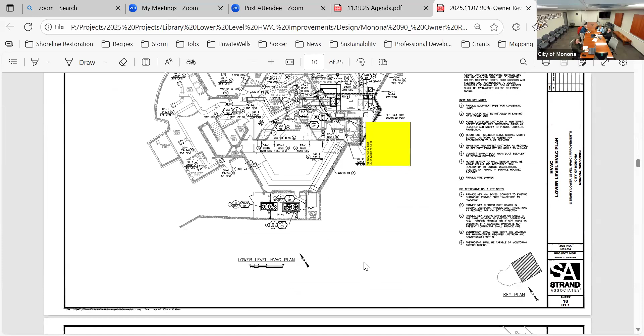We are also going to be replacing the heating coils downstairs. Basically that's downstream on the ductwork, far from the air handler. In a dedicated space, there will be this little hot water tube in the ductwork, and the air will blow over the hot water tube and reheat the air, because the air will cool slightly as it goes through the ductwork. And that just helps as an extra boost of conditioning for the space. We're going to replace those with VAV units because they're more efficient and you can dehumidify with those.